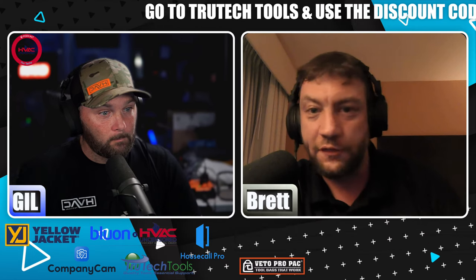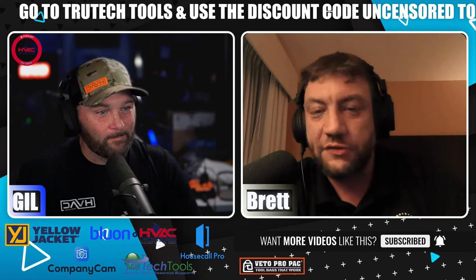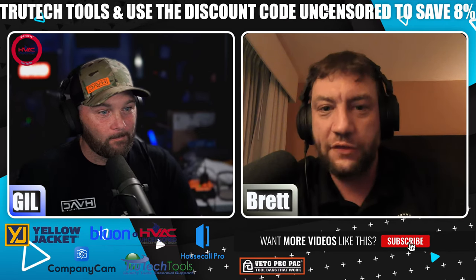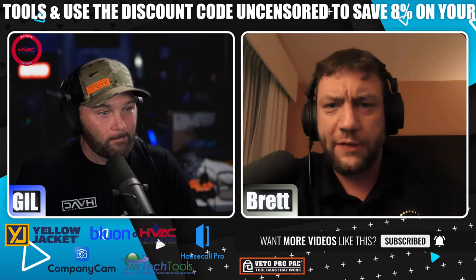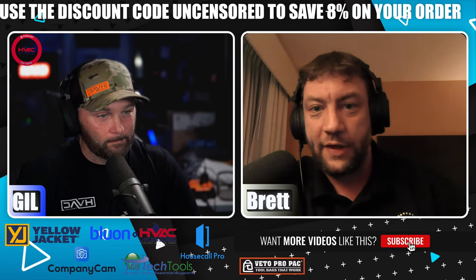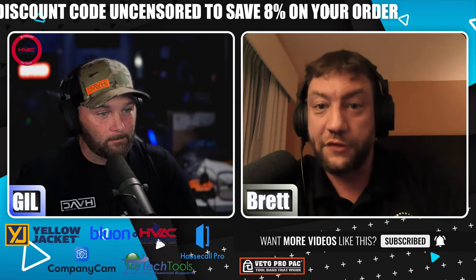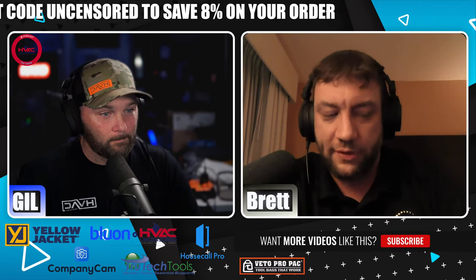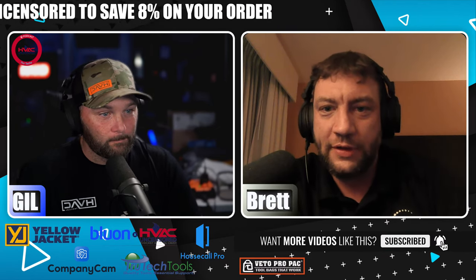They've been using CO2 for a long time - the first patent for it actually came up in the 1850s. They used it a lot for marine applications because you could use water cooling, which kept it subcritical - you've got nice cold ocean water, so you're not running those crazy pressures. I have a picture of a guy with awesome 80s socks and loafers working on a CO2 compressor, from back in the 90s. When R12, 502, and 22 came out, they said 'hey, we don't need to worry about that crap anymore,' so they stopped using it. Then we found out all those other refrigerants we came out with are bad for the environment, so now we're back to CO2.